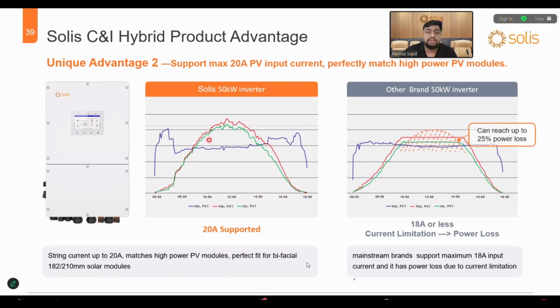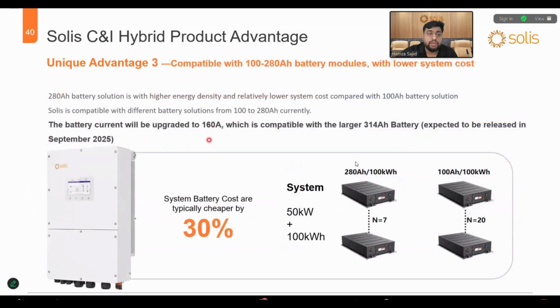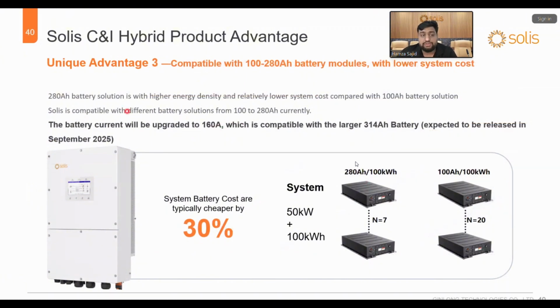So it can easily accommodate the high-ampere modules available in the market. One more thing is Solis is compatible with a 280 Ah battery solution and a 100 ampere battery solution as well, because it has 140 amperes for charging. So it can easily be utilized with a 280 ampere battery or a 100 ampere battery. Like if you check a 50 kilowatt system having a 50 kilowatt hybrid inverter and 100 kilowatt hour backup.